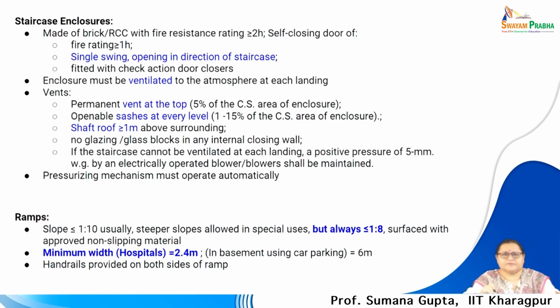Stair enclosures should be made of 2-hour fire rated materials. From the material point of view, we have to understand that a permanent vent system should be there at the top, which is 5% of the cross sectional area of the enclosure. Every floor should have openable vents, that is, a louver kind of attachment, and the percentage of the cross sectional area is also given. There should not be glazing, glass blocks or any internal closing walls. So, within the staircase there should not be any obstruction.